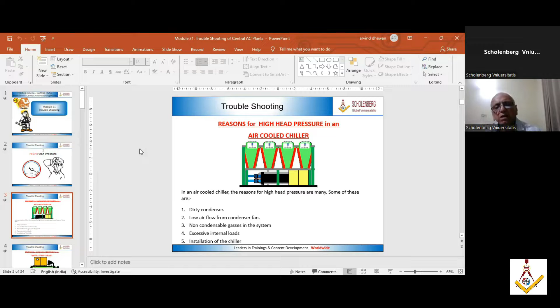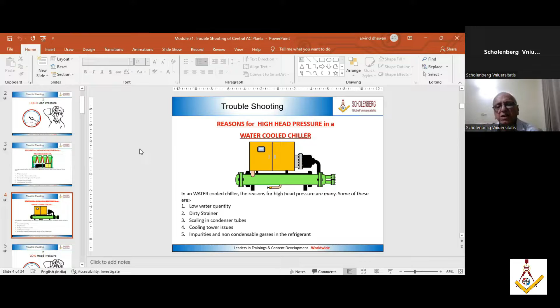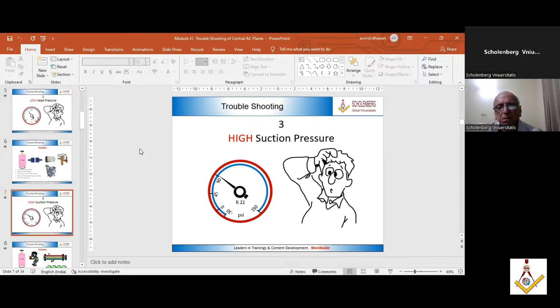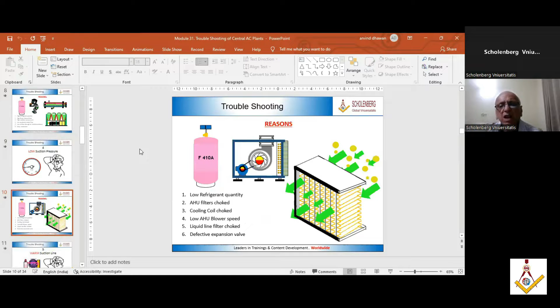Reasons for high head pressure of a water-cooled system: less water flow, dirty strainer, scaling in condenser tubes, cooling tower issues, impurities or non-condensing gases in the refrigerant. Then you have low head pressure. Then you have high suction pressure. Reasons are given, low suction pressure, and the various other issues. Reasons are given here. Then you have warm suction line, and cold suction line. So many other reasons, like shortage of refrigerant, are there.